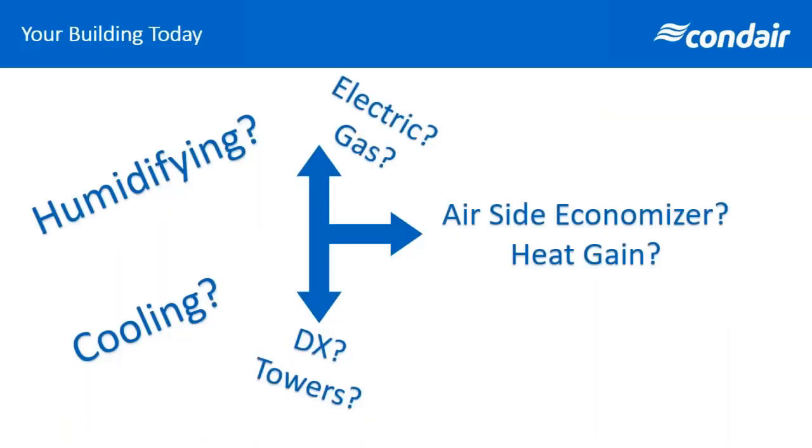Now, this all sounds complicated, and this slide doesn't help because it is actually relatively complicated. But the point I'm trying to make here is that even in the smaller loads, even in the 100% outside air, your evaporative system, if you choose to go to an evaporative humidification system, will use at most the same amount of energy as a steam system and will probably cost you less.